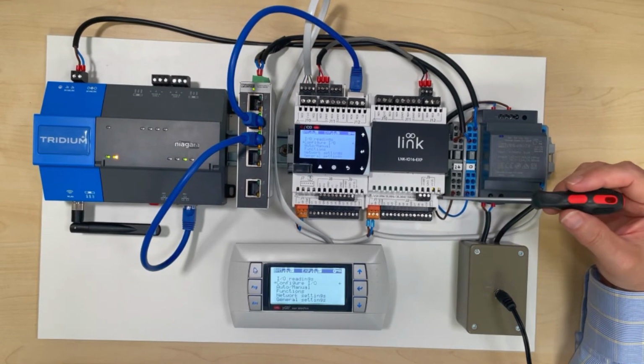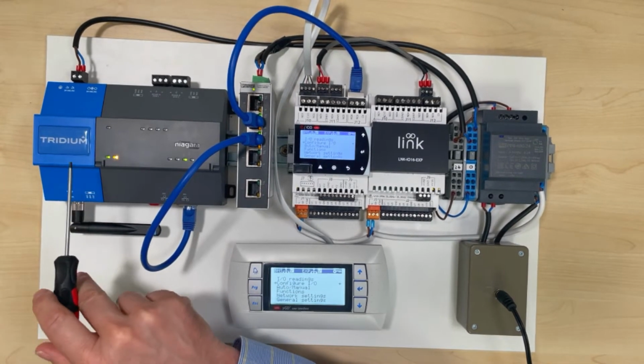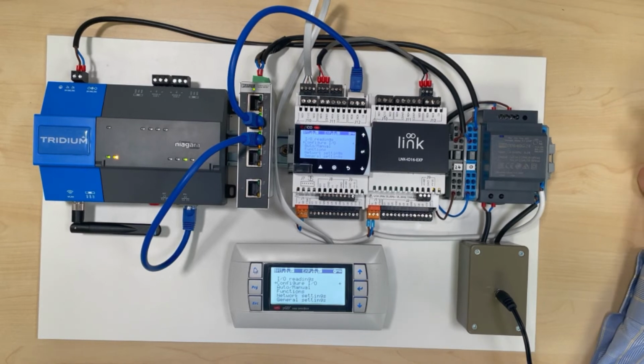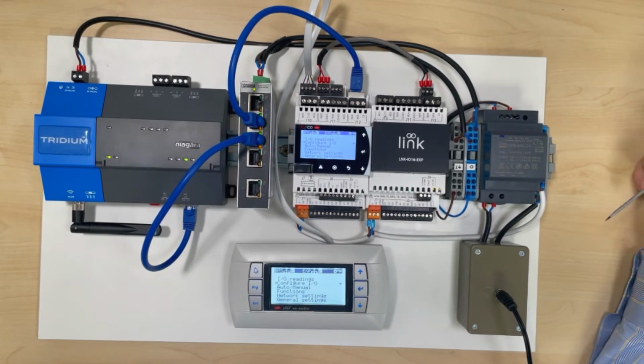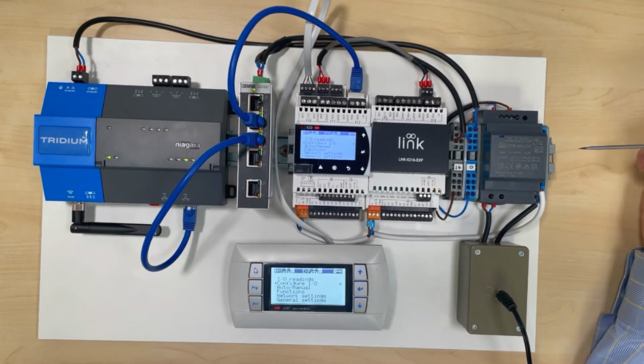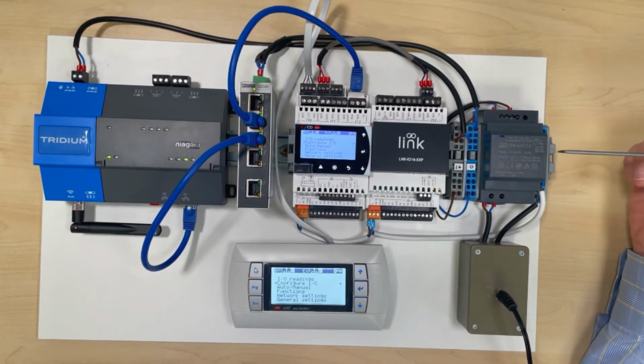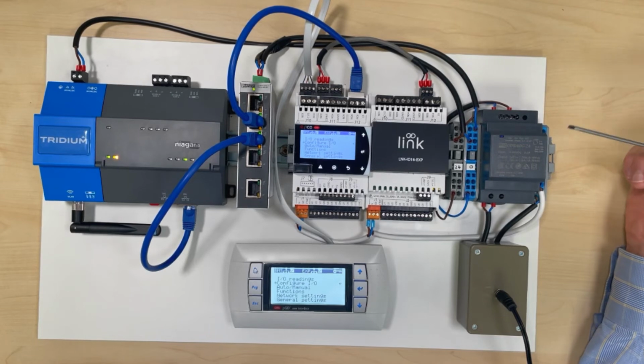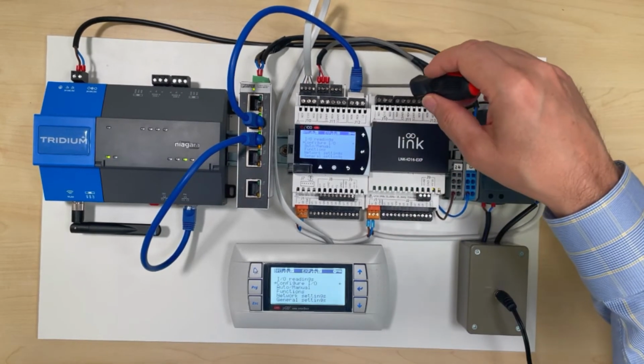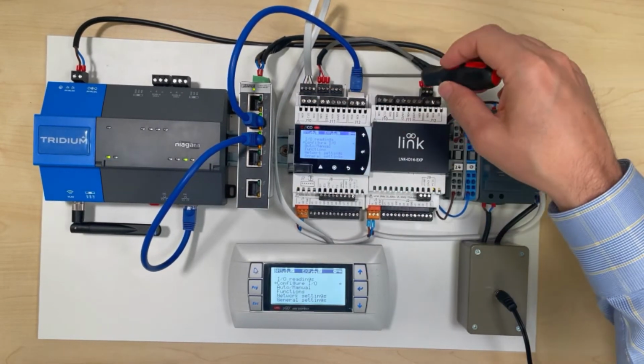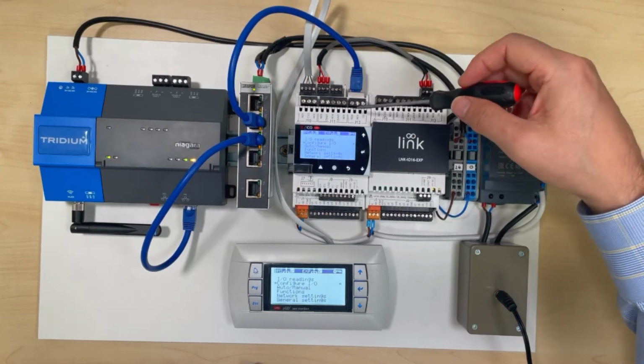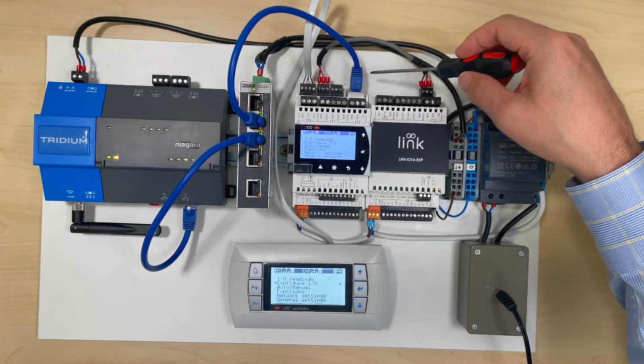Okay, so as we said, we've got a master here. We're using a JACE. You could use something like an IQ4 integration, anything that talks Modbus or BACnet over RS485. So it could be Modbus RTU or BACnet MSTP. Anything that's capable of that can do it. So like I say, I'm using Modbus TCP over Ethernet. If I was using the RS485 version, there'd be an RS485 connector here, and I could connect it to my JACE using one of these ports here.